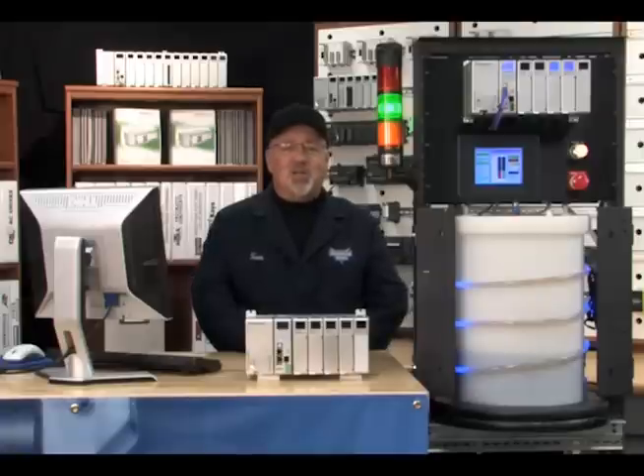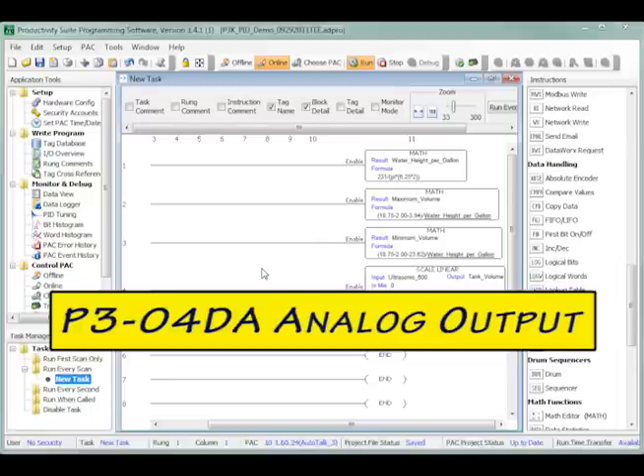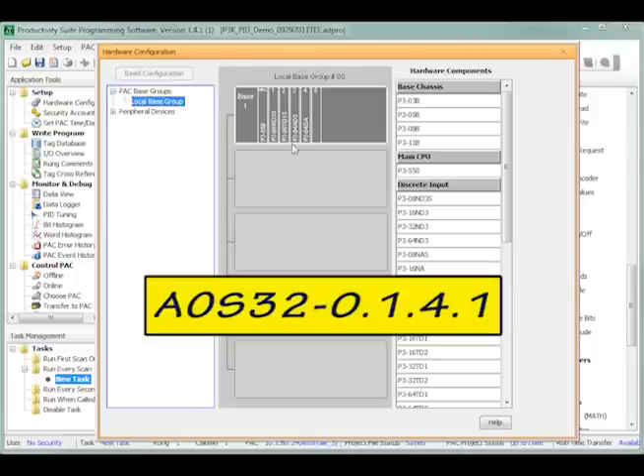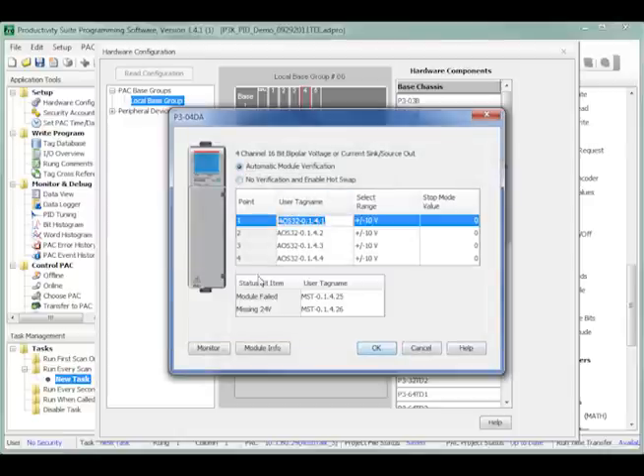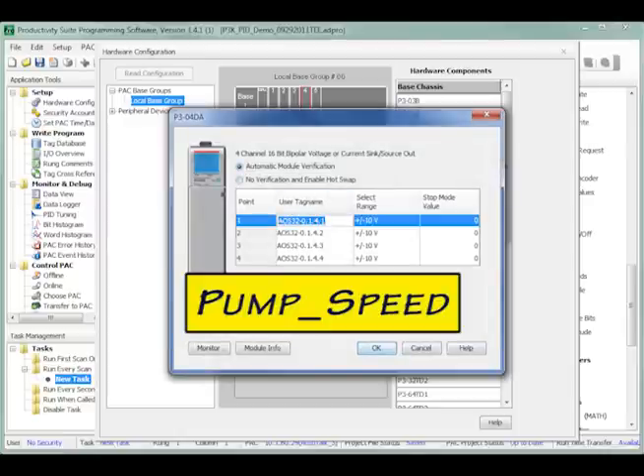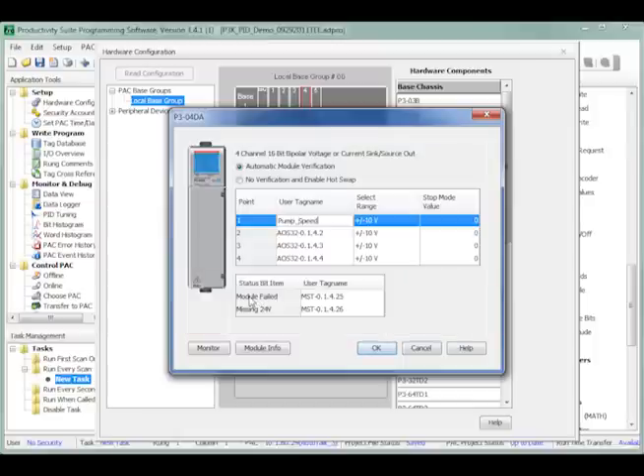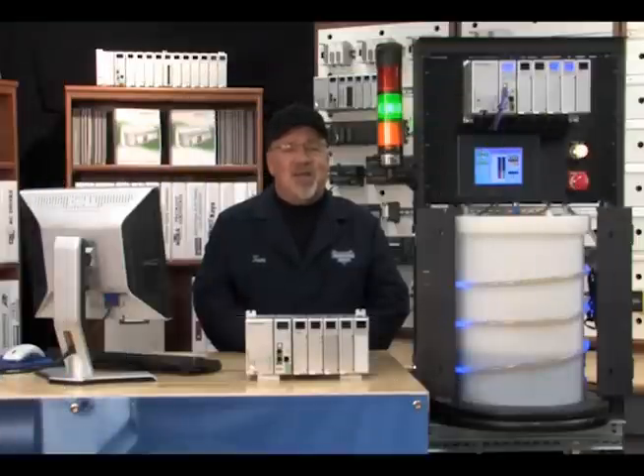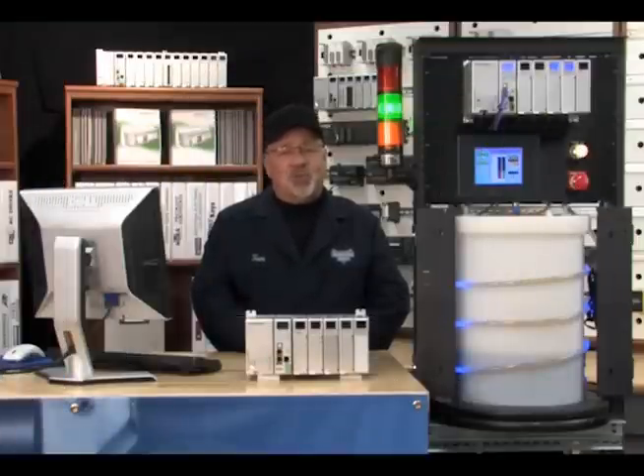Again, using the hardware configuration tool, create a tag name for the P3-04DA analog output module's first channel AOS32-0.1.4.1 and rename it as pump_speed. This tag name will be used in our PID loop instruction and represents the calculated rate the pump needs to operate to maintain the water level in the process tank. The rate will be somewhere between 0 and 1 gallon per minute.